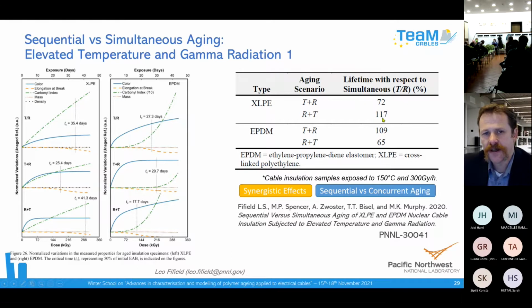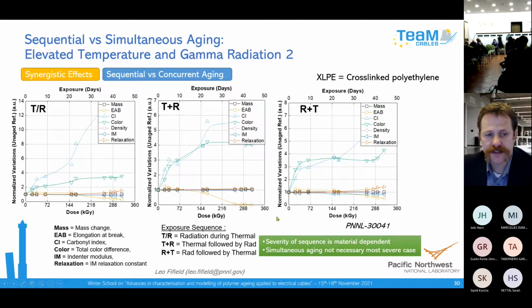In some cases, the sequential exposure was more severe than the simultaneous exposure that you might see during a cable's service lifetime in the plant, and sometimes it was less severe. So you have to look at the details of the material to make those predictions. The conclusion is that the severity of the sequence of exposure is material dependent. One concern was that in a plant, cables are exposed to gamma and heat at the same time, whereas in accelerated aging one comes after the other. If simultaneous exposure is more severe, then we are overestimating lifetime and will have more failures than anticipated. But one of our conclusions was that's not necessarily the case. In some cases, the simultaneous exposure was actually less severe.